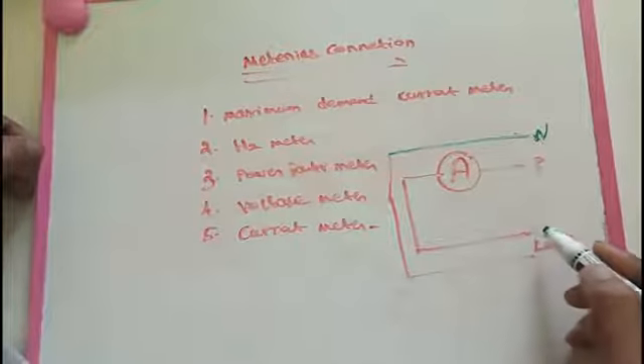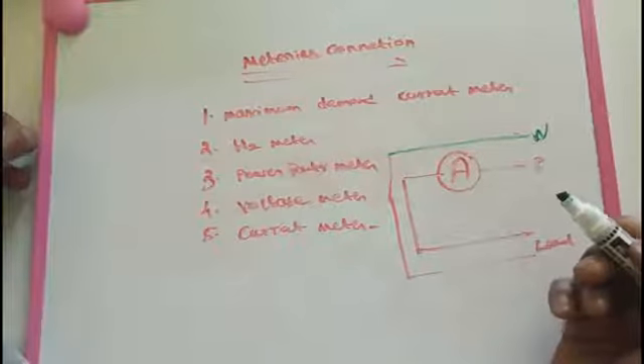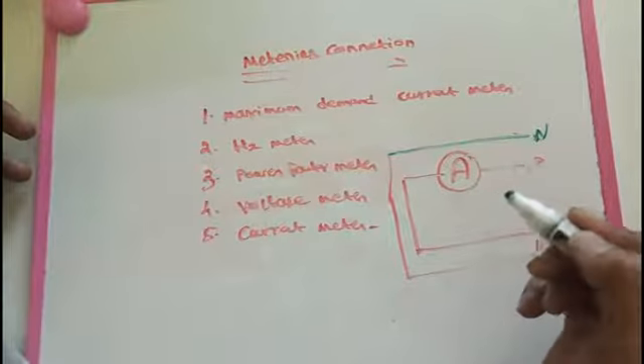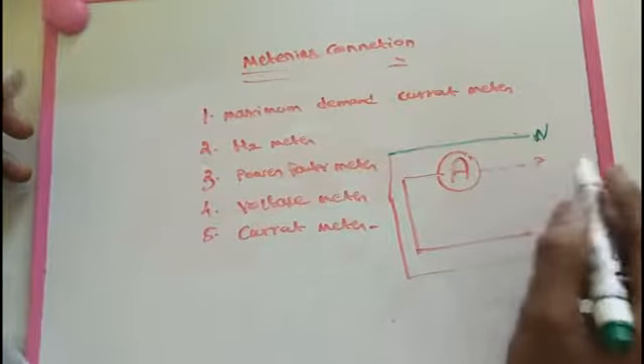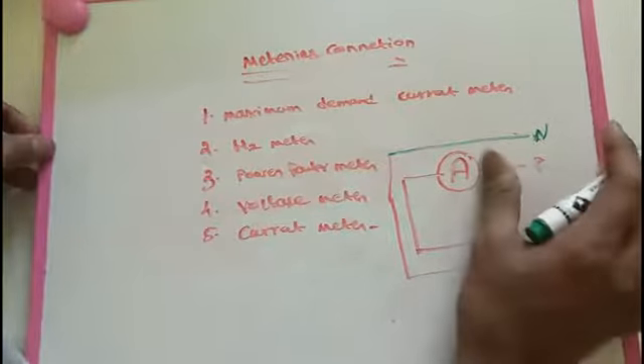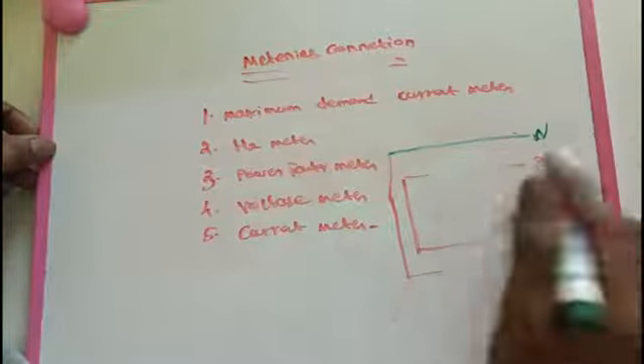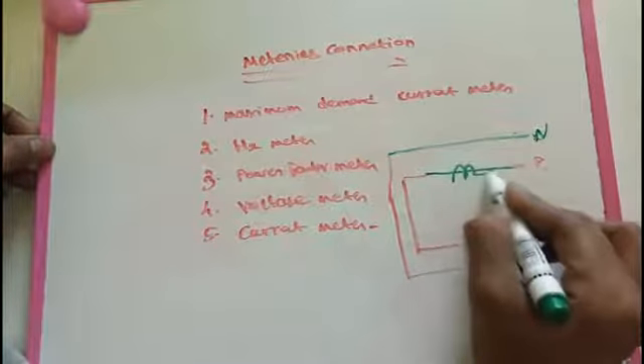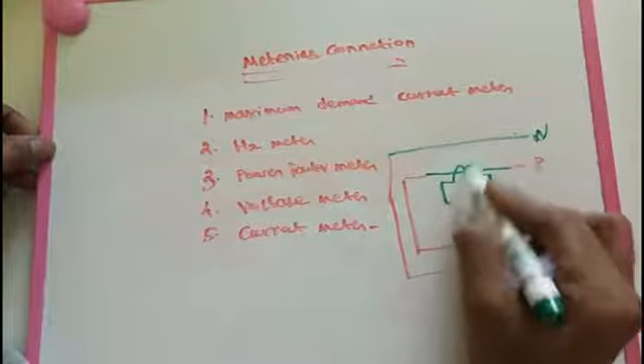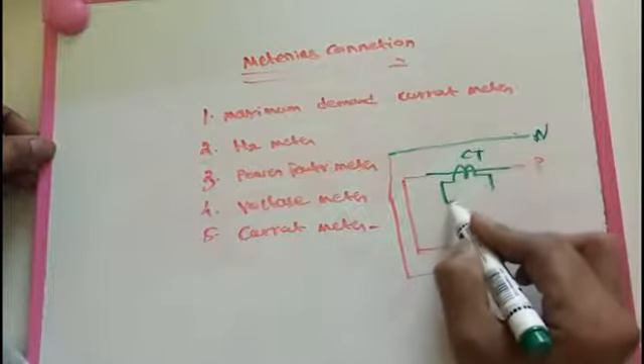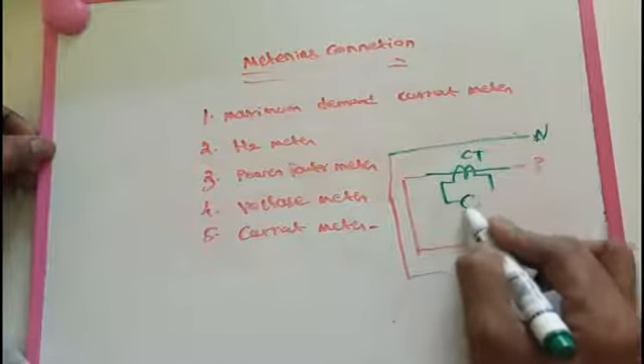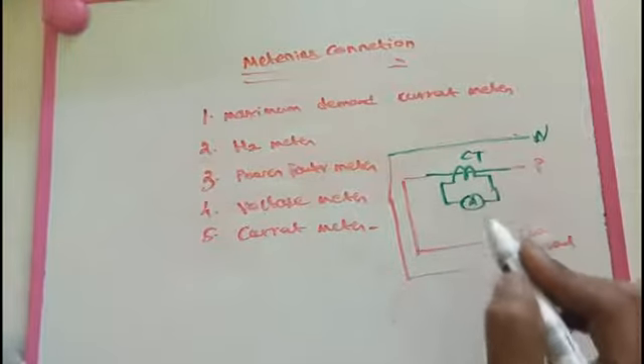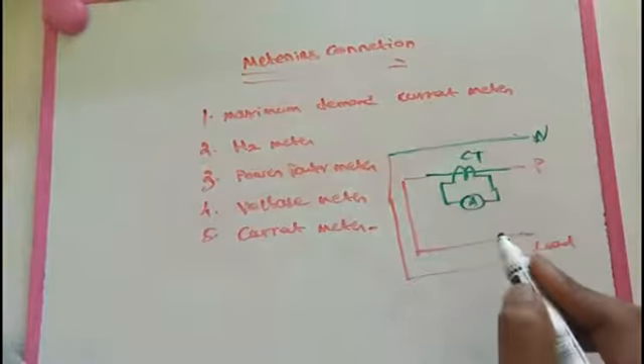If a higher range of current flows, we cannot use a direct ammeter for that rating. In that case, we use a current transformer. We install the current transformer and give a stepped-down output to the ammeter. This is the condition for connecting an ammeter with a CT.